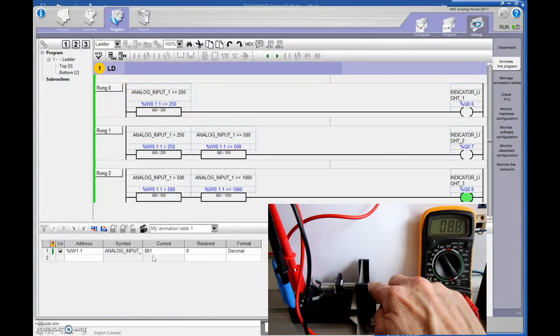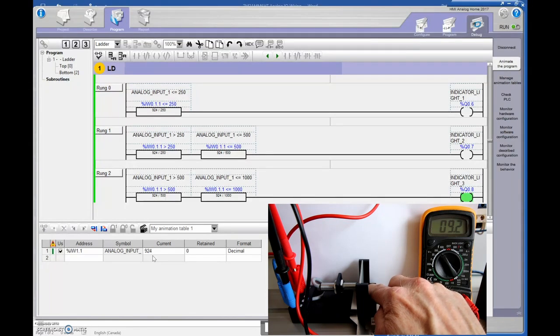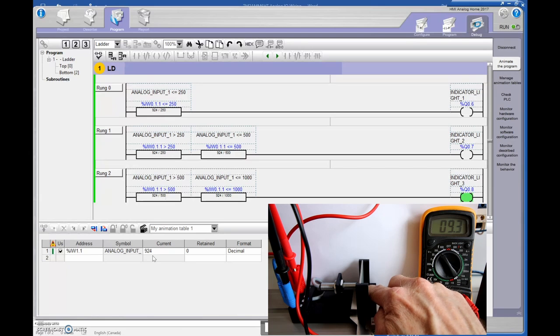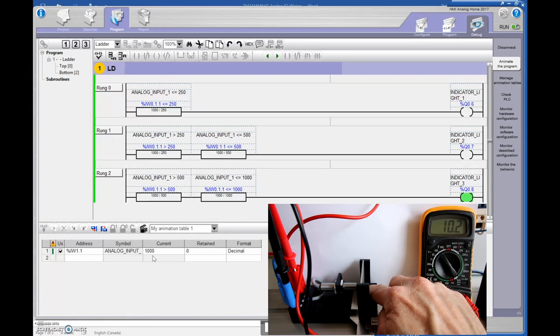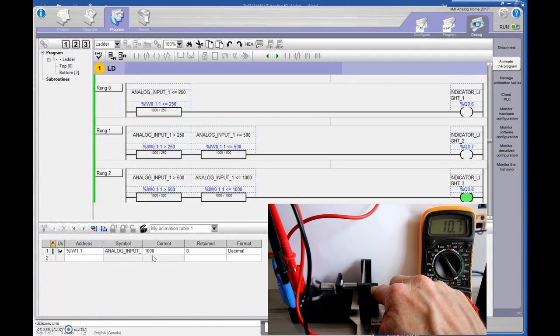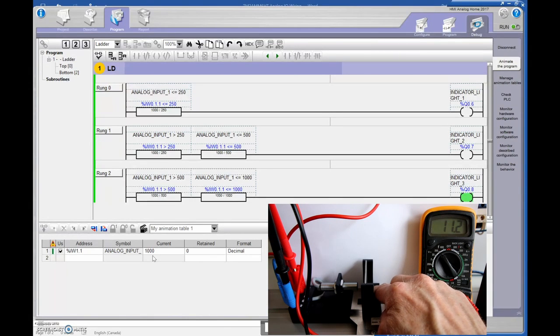9.2. You can see that value mimicking on the PLC there. And we'll go up to 10 volts. And you can see that we're at the maximum of 1,000. Now I can go above that value, but the PLC range is only from zero to a thousand. Right. So it can only read zero to 10 volts.